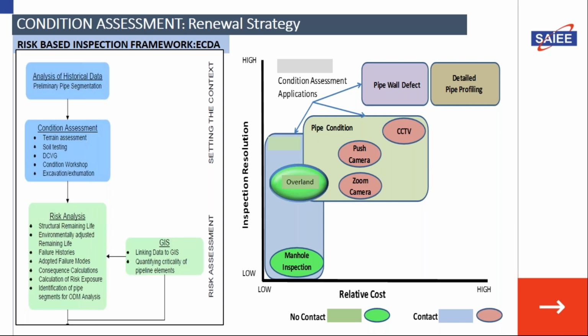Once you've analyzed the historical data, you look at the parameters of your pipeline. Is it a steel pipeline, or a pre-stressed concrete pipeline? What types of joints do you have? Some pipes are continuously welded, some are spigot and socket jointed, that is lead caulk jointed. Look at all that information: the age of the pipeline, the maintenance history, the failure history. After that, you look at the condition assessment approach you need to employ on the pipeline.